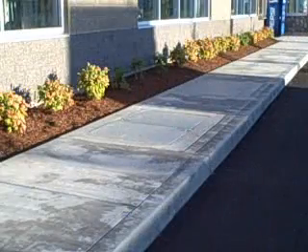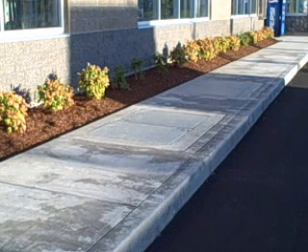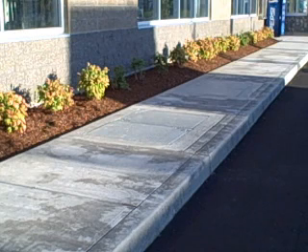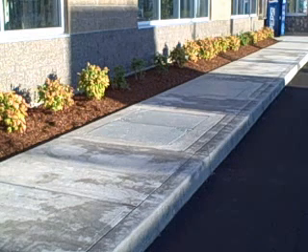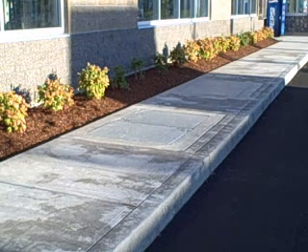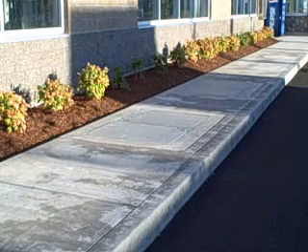Here we have 2 reclaim vaults. Each vault has 2 750-gallon compartments. We place 1 pump in each compartment of the first reclaim vault. The first vault will contain most all of the sediment and sludge coming from the conveyor trench. In the case of an automatic rollover, we can place 1 pump in the catch basin in the car wash bay and another pump in the reclaim vault. We can also custom tailor a pit manager system for a self-serve car wash and also for your specific operation.